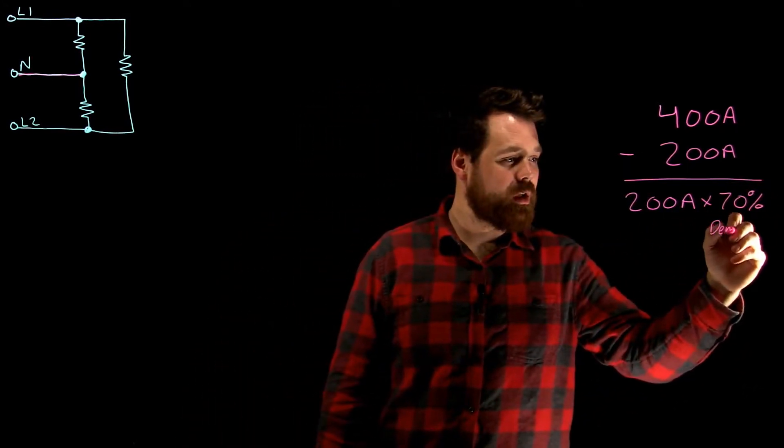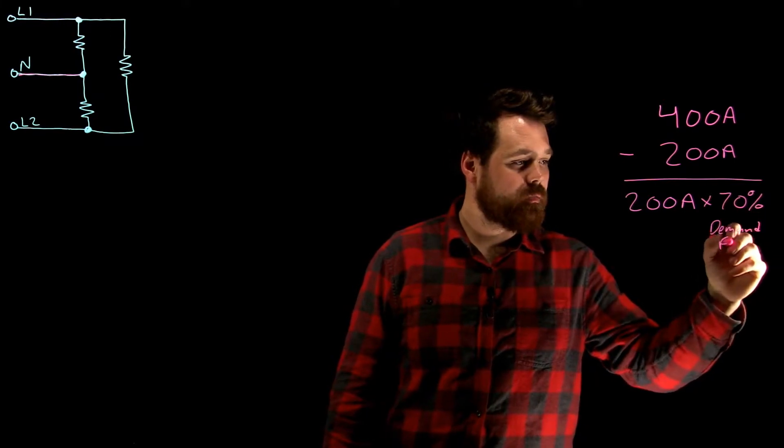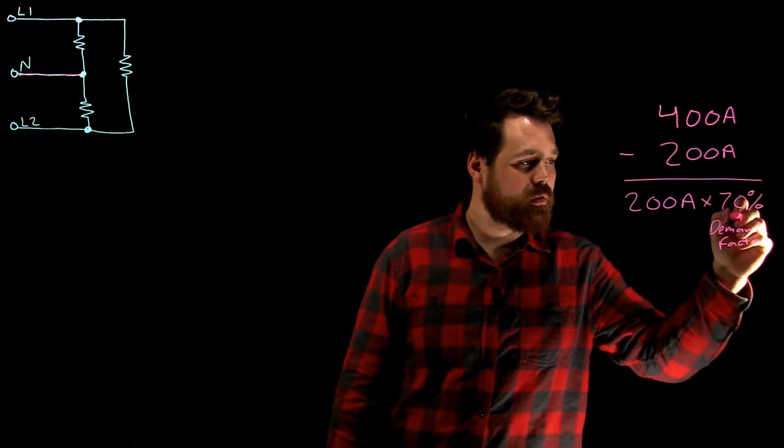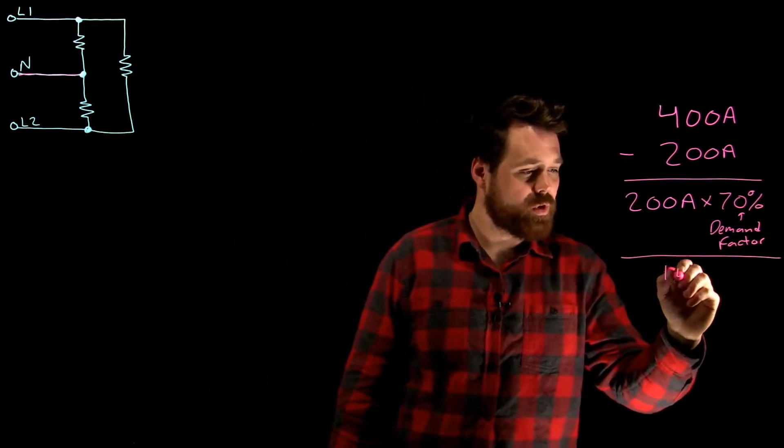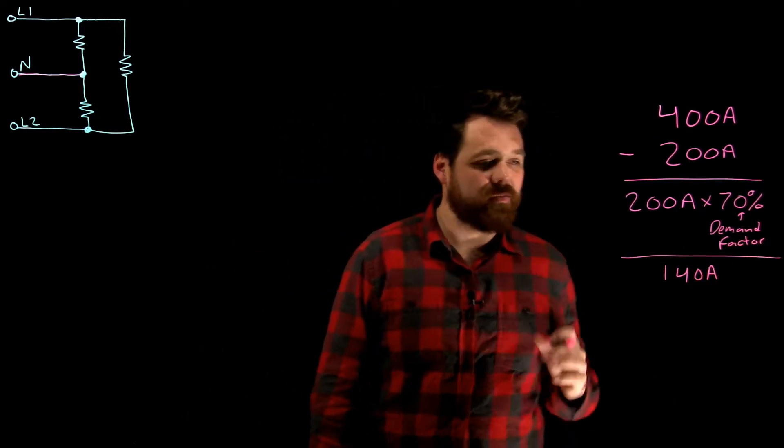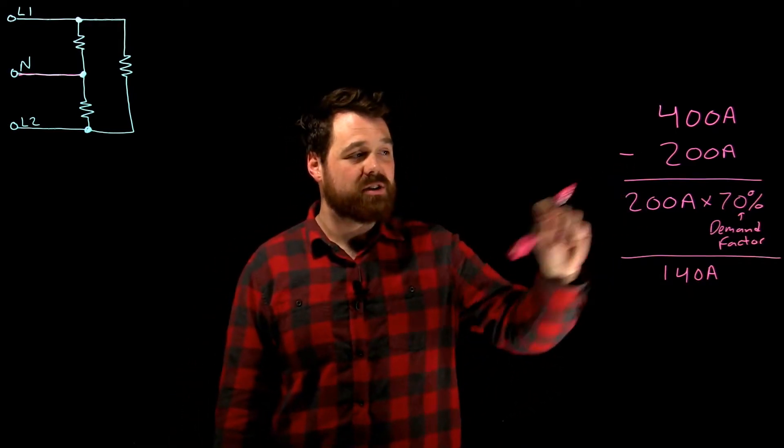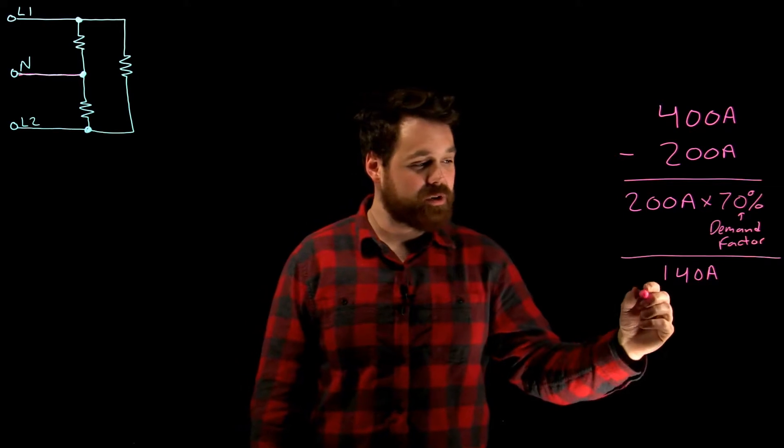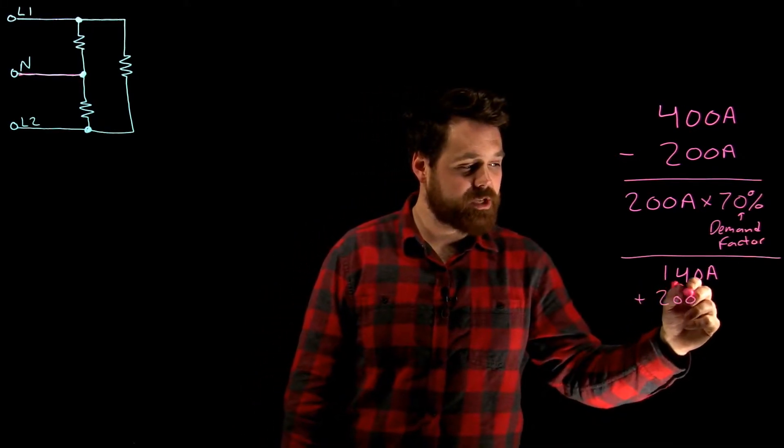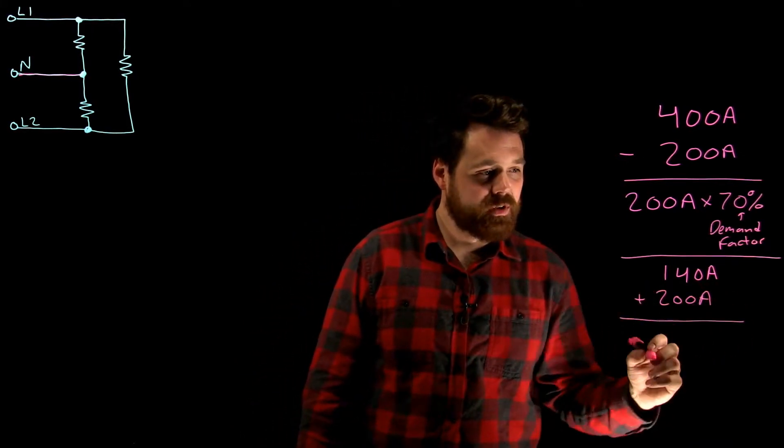We multiply that by the 70% demand factor. That's the demand factor, right? And that is going to give us in this case 140 amps. So we've applied a demand factor to everything exceeding 200 amps. What we need to do now is we need to add back in that original 200 amps that we took out.